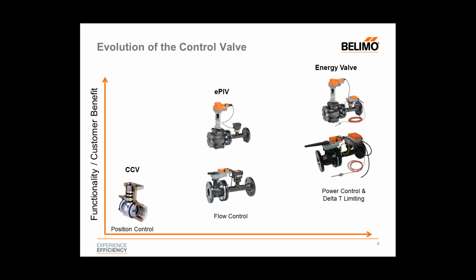Around 2003, we introduced the PICCV, which is a mechanical pressure-independent solution. And we followed up with another introduction to that mechanical pressure-independent solution last year with the PIQCV. But what we're talking about here today is electronic pressure independence. So achieving pressure independence not by a mechanical pressure regulating system, but by using a flow sensor and control algorithm based within the actuator. So what we'll talk about here today is both the ePIV and energy valve, so you see a little bit of the legacy of how these were derived.